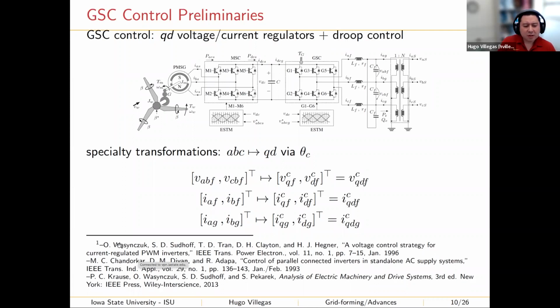One characteristic of the paper, A Voltage Control Strategy for Current Regulated PWM Inverters, is that they use the synchronous reference frame. In fact, the speed of the reference frame is maintained fixed. So now we can adapt this for system level by using the droop control. What we start with in the controller is transforming variables, for example from ABC into a QD system via theta c. Theta c is the integral of the speed from the droop control law.